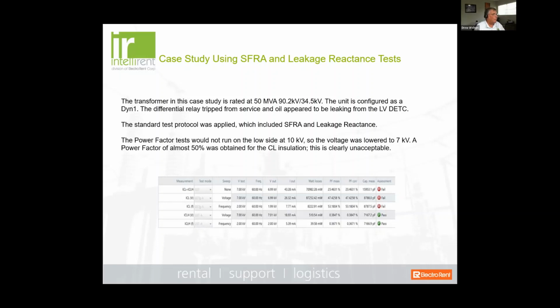All right, this is a 50 MVA transformer configured as a DY1, and the differential relay tripped from service, and oil appeared to be leaking from the low voltage de-energized tap changer. Okay, and that's a tap changer that's embedded into the tank of the transformer. Your standard test protocol was applied, which included SFRA and leakage reactance. So unfortunately, in this case, the power factor test wouldn't even run at 10 kV. So they lowered the voltage, of course, and they pushed through, and the power factor was almost 50%.